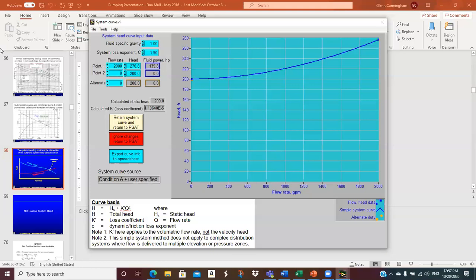So let's say that we just changed it a little. Let's say for our system we had 50 feet of head. There we go. So you get a curve like that. Well, that's all it takes. Here's my static head. It's whatever I put in at zero flow. So H sub S is 50. Here's my loss coefficient, my K prime, which is 1.21257 times 10 to the minus 4. And there's my exponent.